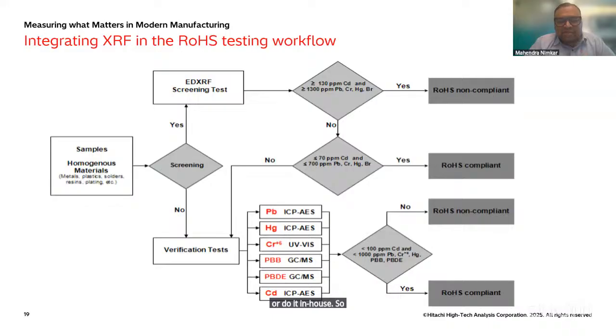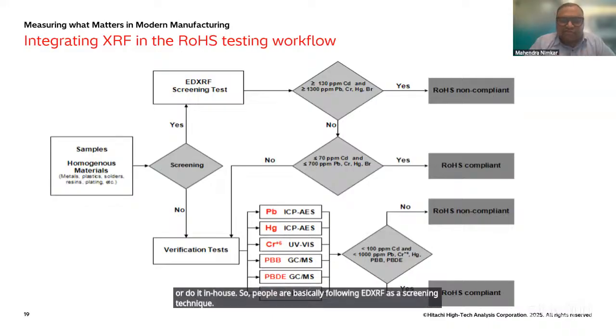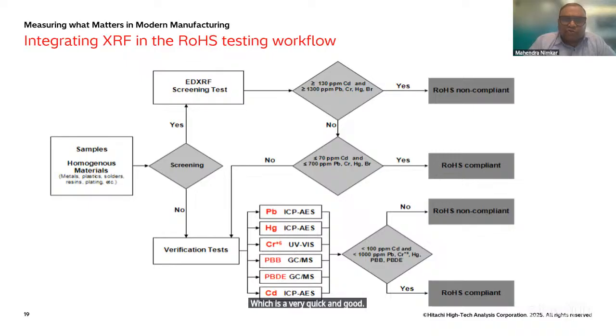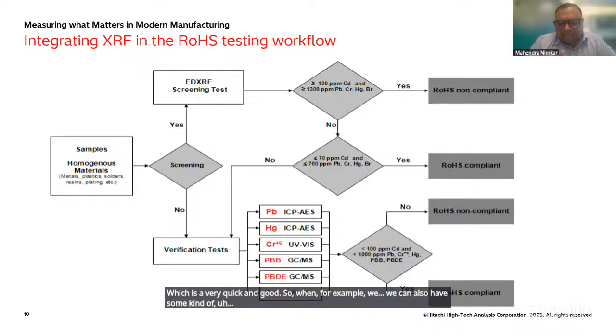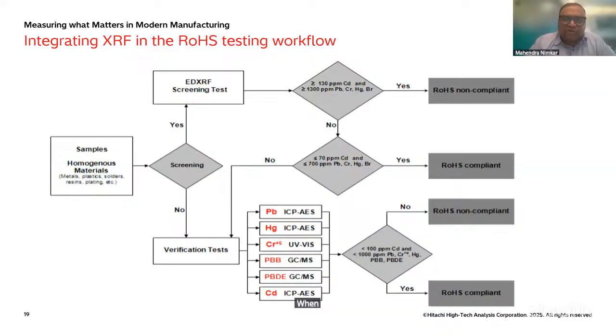So people are basically following EDXRF as a screening technique, which is very quick and good. We can also have some kind of window, I would say. For example, when you do screening with EDXRF, let's say the cadmium limit is 100 ppm. If you see the result when you do the screening with the EDXRF, if it is more than 130 ppm, it is definitely failing. If it is less than 70, it is definitely a pass.